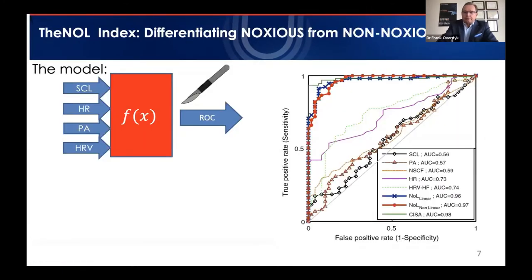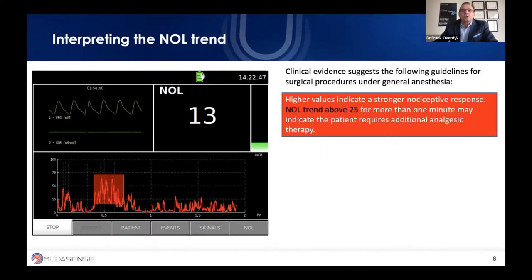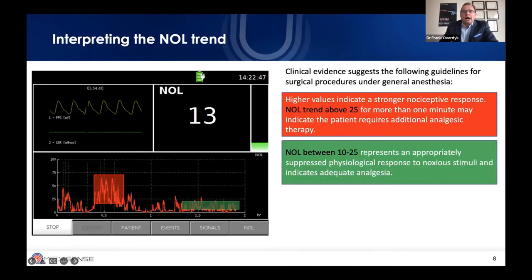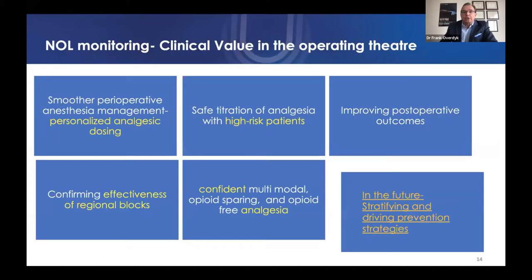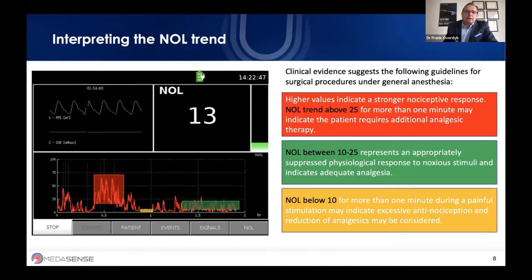The user sees a display showing a continuous plethysmograph signal and skin conductance. The NOL absolute value ranges between 1 and 100 — higher values indicate a stronger nociception response. A NOL trend above 25 for more than one minute may indicate the patient requires additional analgesics. NOL between 10 and 25 represents an appropriately suppressed physiologic response with adequate analgesia. NOL below 10 for more than one minute during a painful stimulus may indicate excessive antinociception, suggesting you may want to reduce analgesics — for example, by turning down the target concentration in a remifentanil TCI.